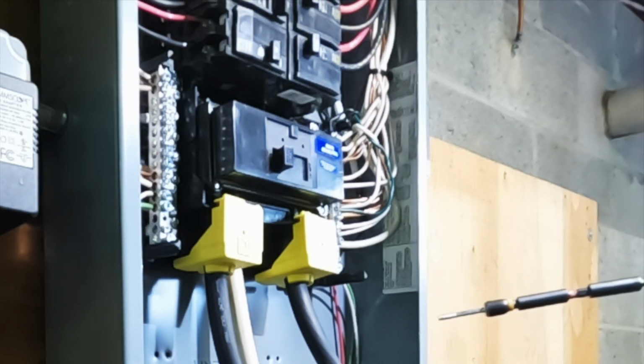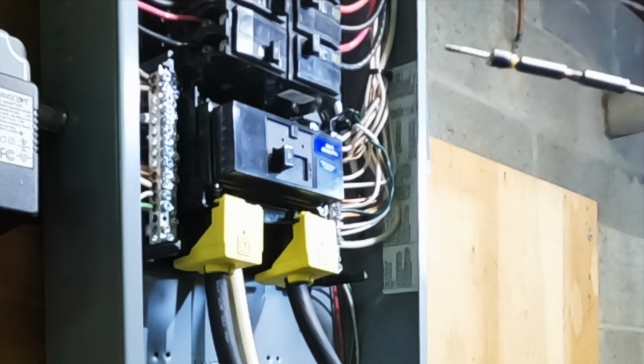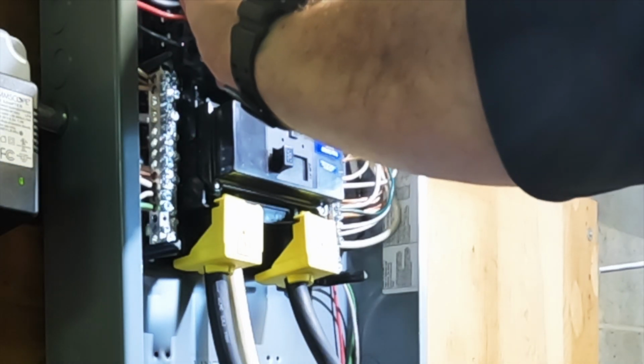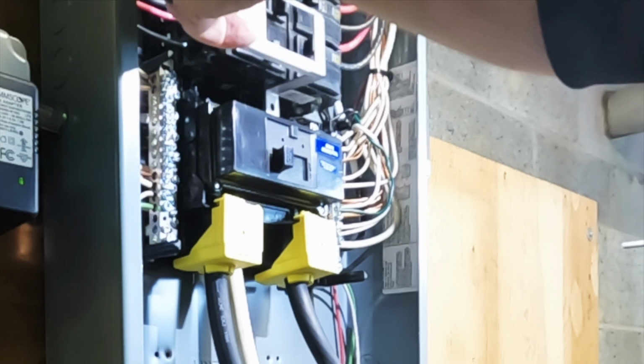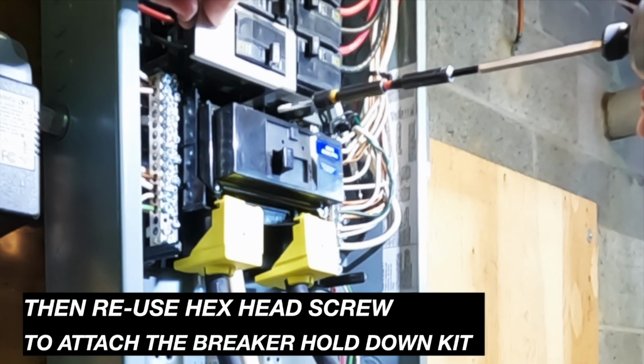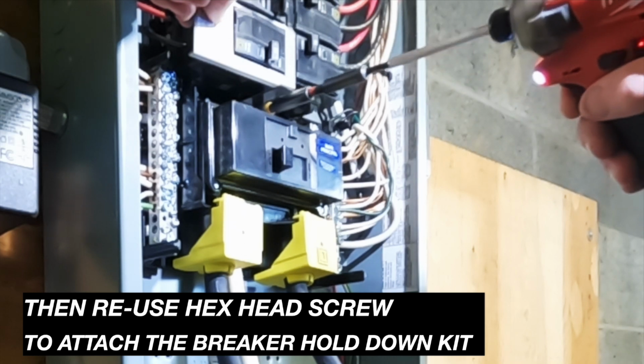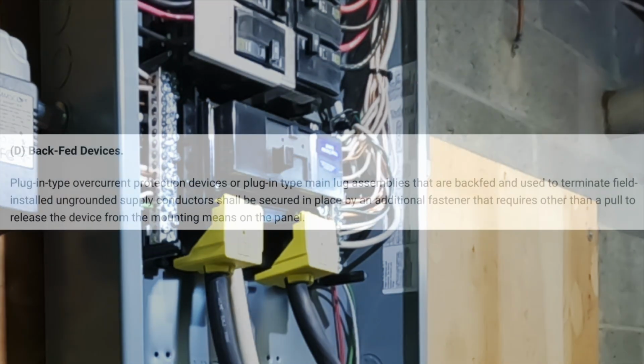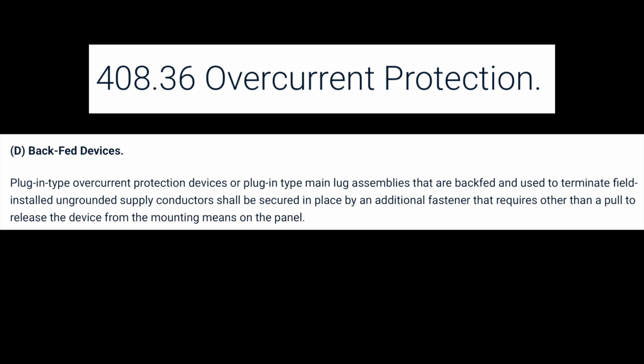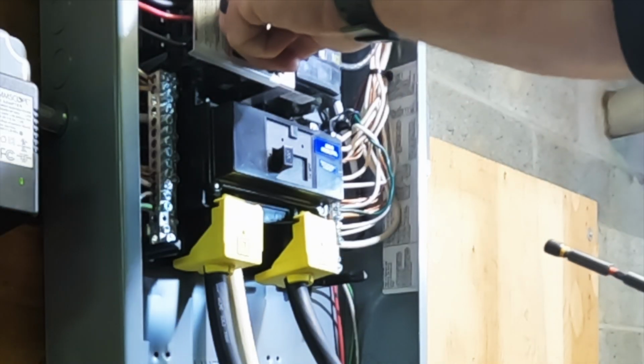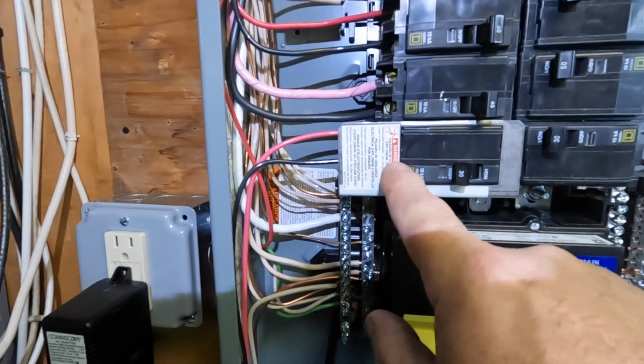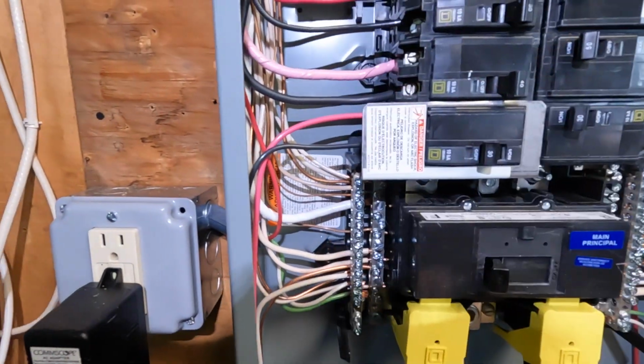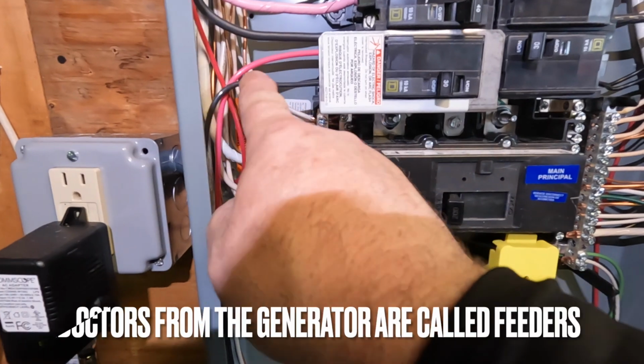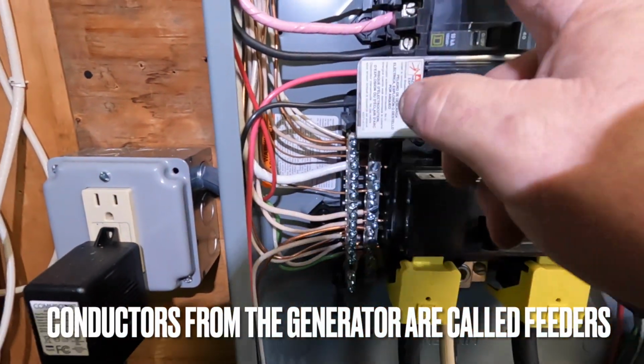And now we are going to put this cover over our breaker, just like this. And be very careful. Those bolts sticking out are live. Okay. And now we're in. This is the code section that requires the breaker hold down kit. So now you can't physically remove this breaker. This cover actually keeps this breaker from being inadvertently pulled out, since this is going to be the supply rather than the load from the bus bar.